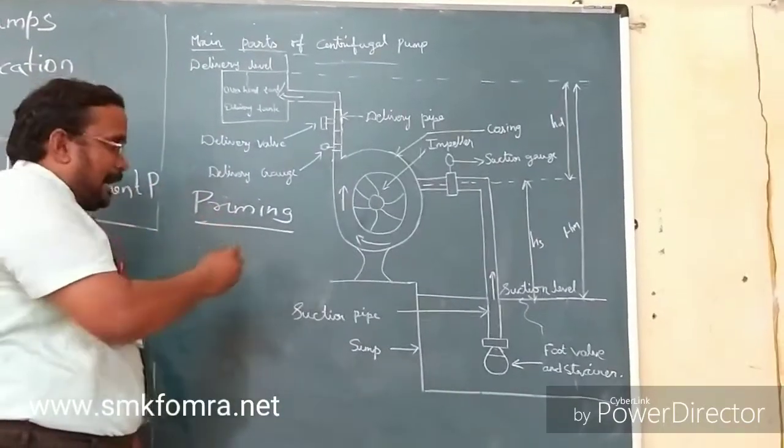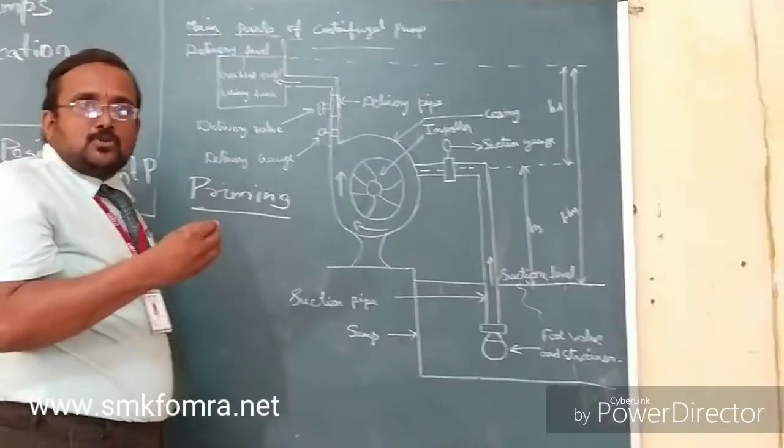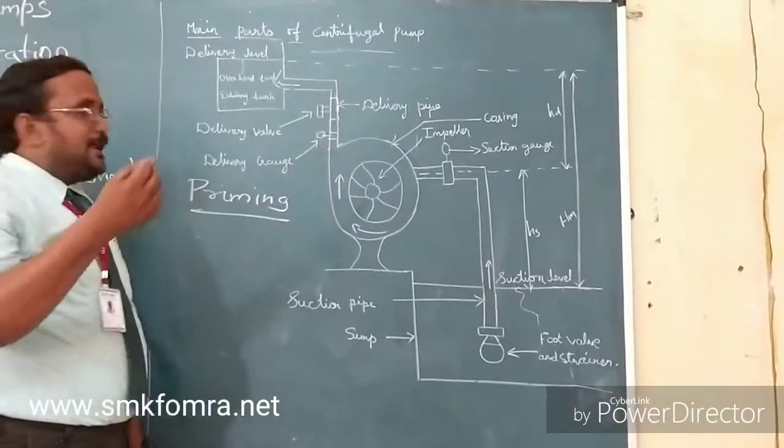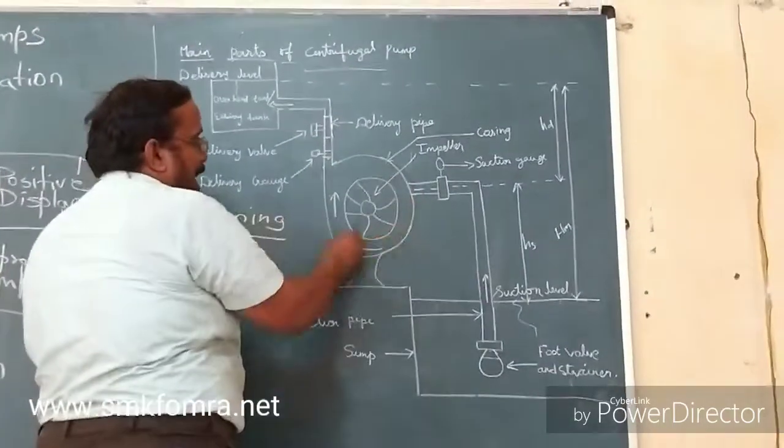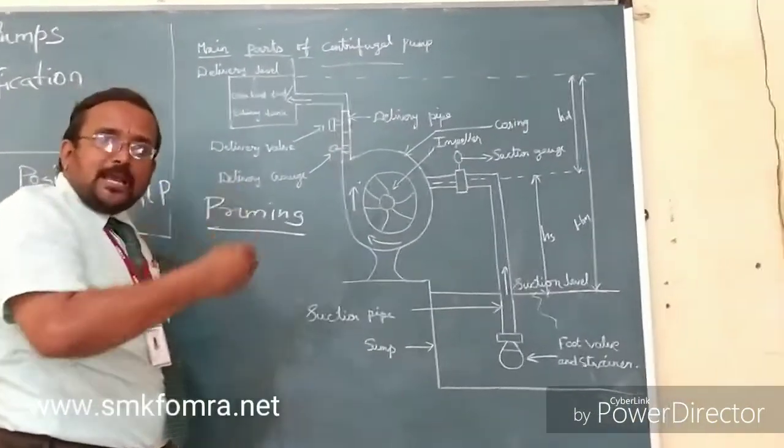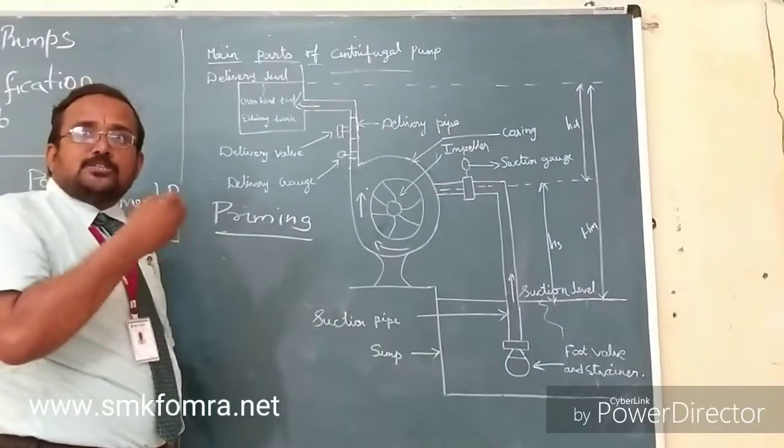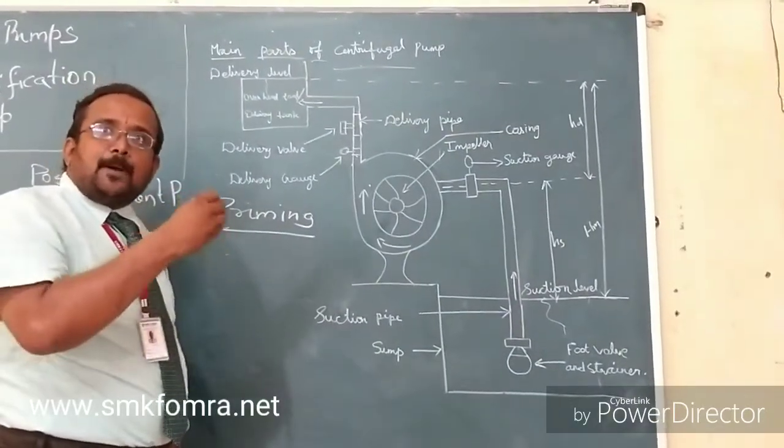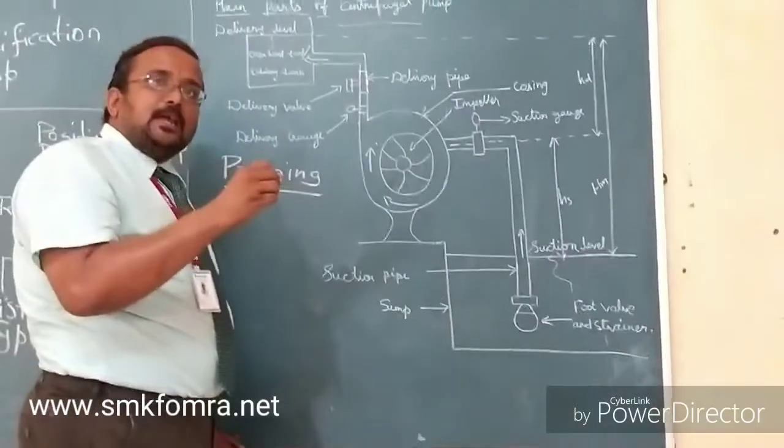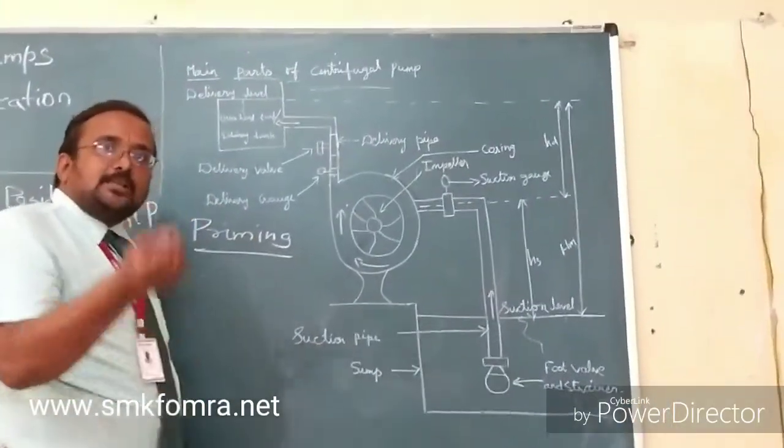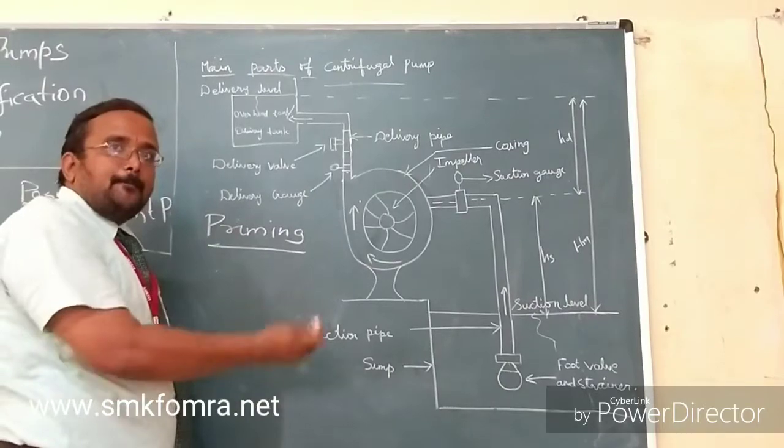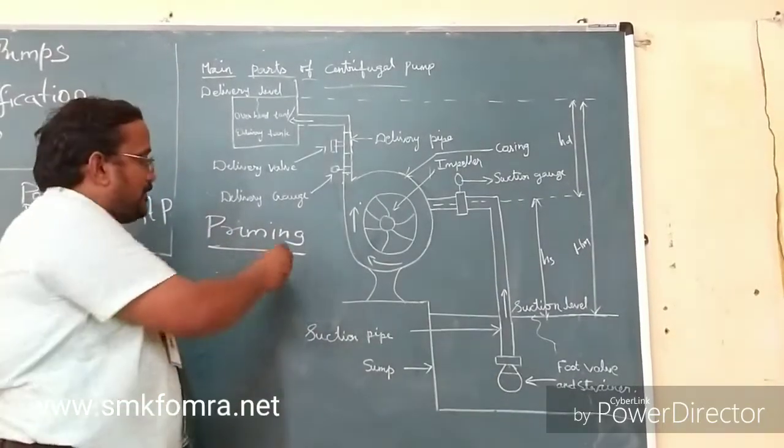Density of air is less than water. So when I rotate the air, the head developed will be less. So I need to fill the casing, the delivery pipe, and the suction pipe with the water. So that when I rotate the impeller at the initial stage, before starting the pump, I will impart certain head to the fluid. That will be proportional to the density. Density of water is more than air. Hence there will be more efficient pumping of the liquid. So that is why we do priming.